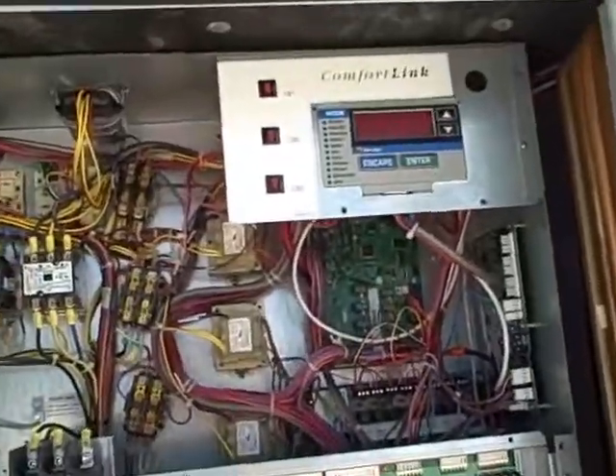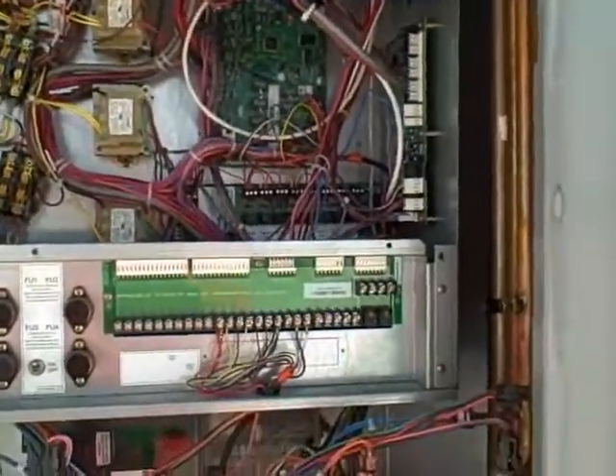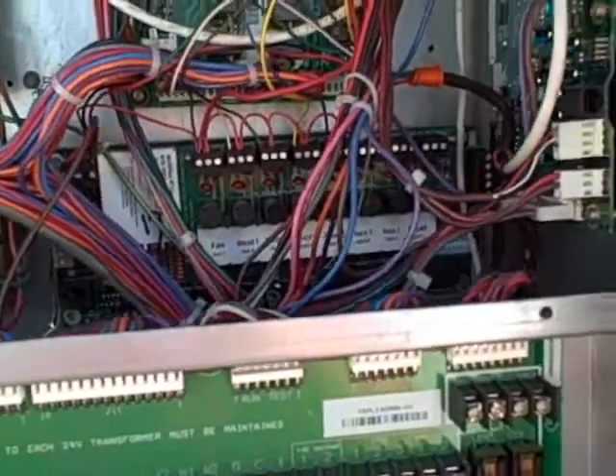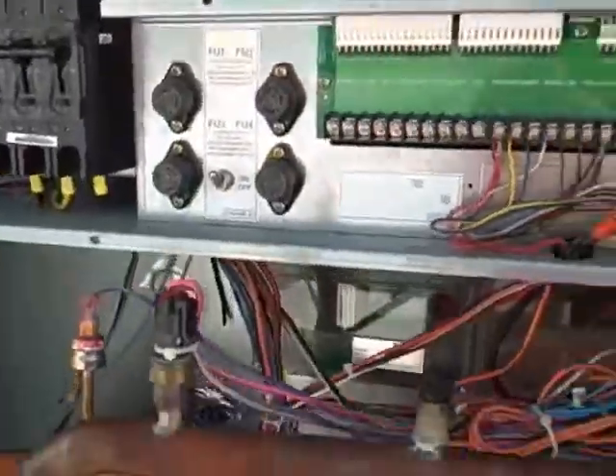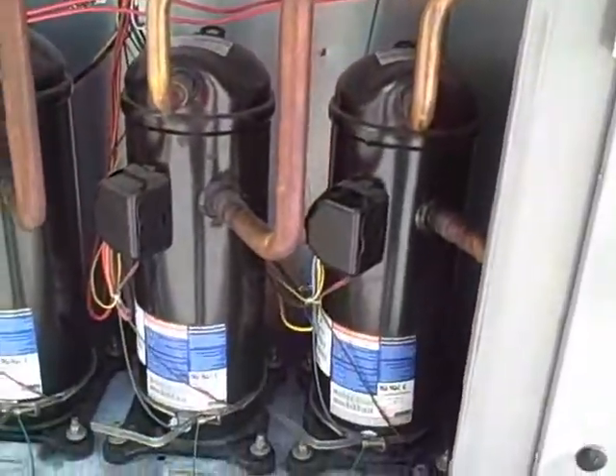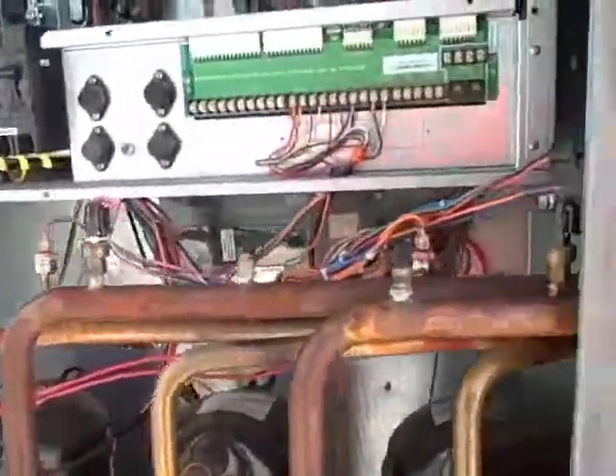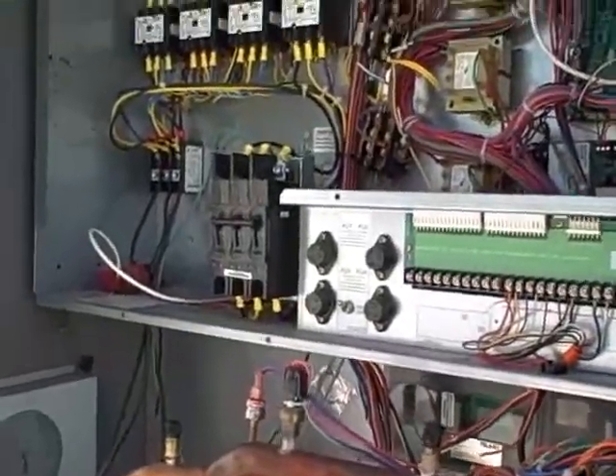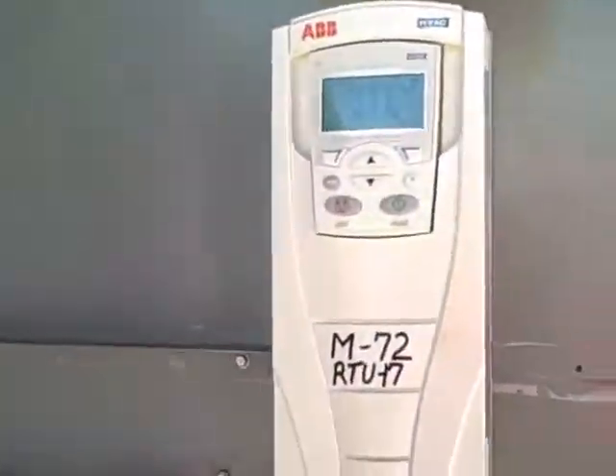This one has ComfortLink control and it's also being controlled by CPC. It's an R22 unit. It has a variable frequency drive on the blower motor — this one happens to be an Allen Bradley.